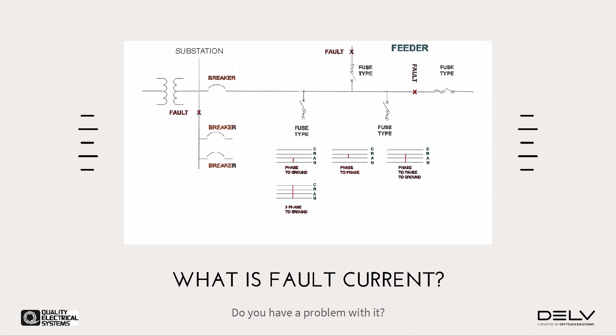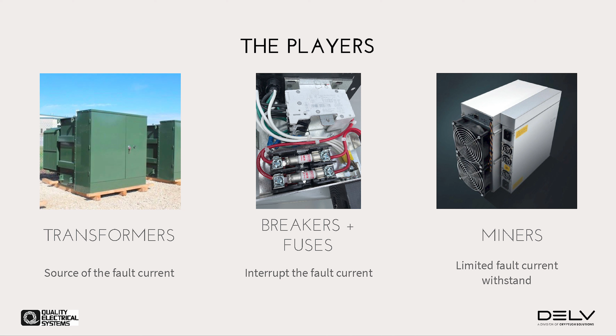When you look at a one-line diagram, this is a pretty simple one. The size of your transformer is basically what dictates how much arc flash you have. A good rule of thumb is that whatever the full load current on the transformer is, if your transformer is capable of producing 2,000 amps of full load current, it is capable of producing approximately 18 to 20 times that much fault current. So if you've got a transformer that can produce 2,000 amps to feed your miners, which is approximately 1 megawatt worth of miners, you are looking at something that can produce 40,000 plus amps of fault current. So if a 22K fault is like getting hit in the face by Mike Tyson, with a 40,000 amp fault, the shock wave alone, not the arc flash, not the burn, just the shock wave alone is potentially lethal.